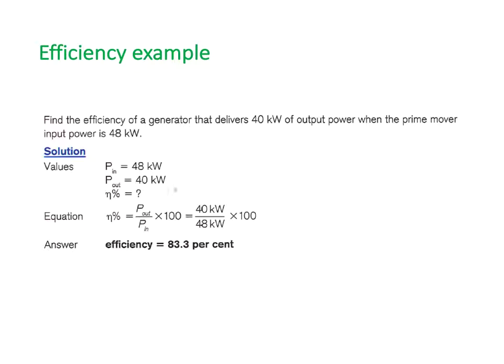Let's do a quick example. Find the efficiency of a generator that delivers 40 kilowatts out when the prime mover inputs 48 kilowatts. So we put 48 in but only got 40 out, losing 8 kilowatts in losses. Using our formula, percent efficiency equals P_out divided by P_in times 100. So 40 divided by 48, multiplied by 100, gives us 83.3 percent efficiency. So 83.3 percent of what we put in comes out as electrical power.